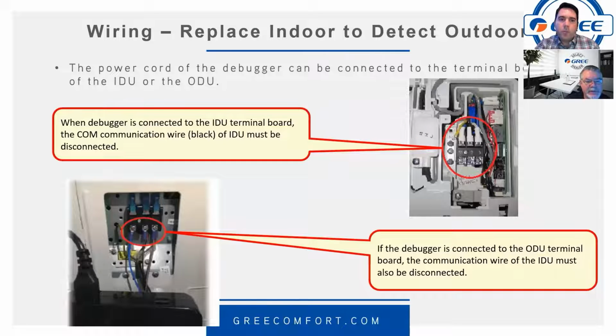And so this is an example of the mini split one, right? Yeah, the single zone. So you've got your 1, 2, 3 wires hooked up, and you can hook up to the indoor or the outdoor, and read all the parameters from that particular model or particular unit that you're attached to. Yeah. So if you hook it up here, you've got to disconnect on the indoor and vice versa.